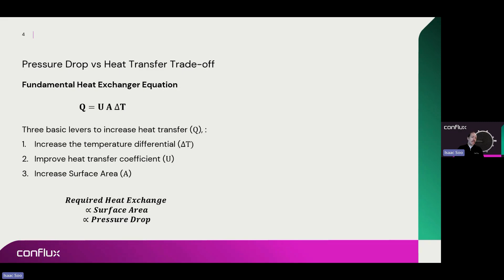It's worth noting that the surface area sits as the linchpin in between heat exchange and pressure drop, and varying surface area has a dual impact on both. You can't maximize the heat exchange and minimize the pressure drop together, at the same time, as easily. There's actually a balance required because these two objectives work in tension with one another.